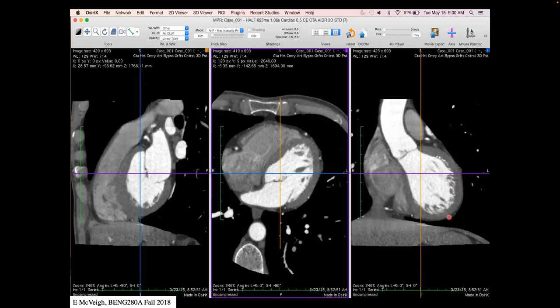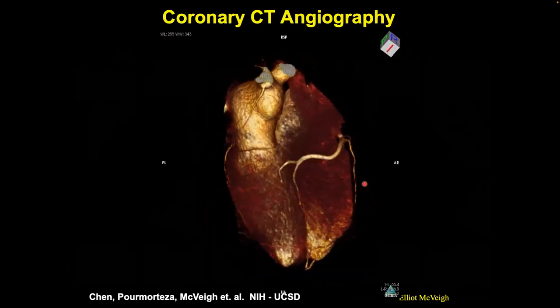The voxel size is approximately 0.5 × 0.5 × 0.5 millimeters — stored as a 16-bit number with that spacing. The resolution as measured by the point spread function should be smaller than 0.5 mm, meaning you want more sampling points than your resolution limit. It's a lot of data, though much less of a burden than it was ten years ago.